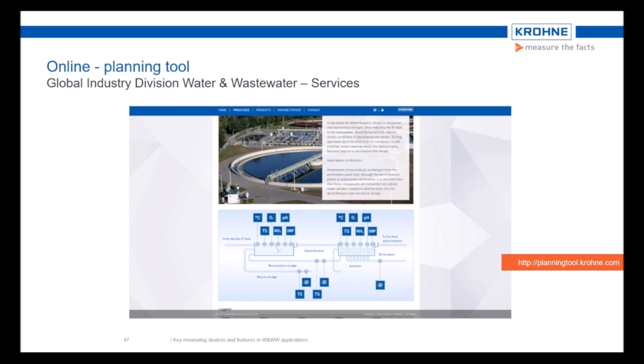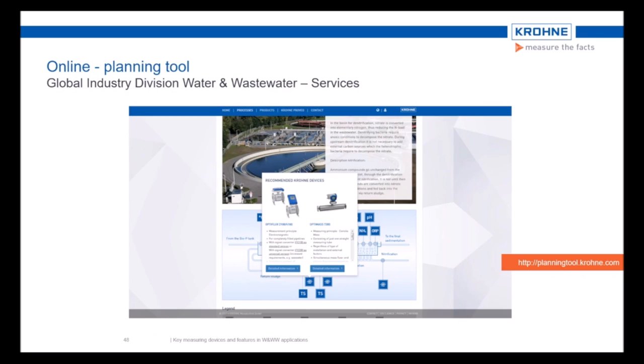Within the graphics, we can see the blue colored icons, which are named and linked to the dedicated measuring devices. For an example, we decide to click the flow button in the return sludge pipe. We then get 2 devices to choose from. In many cases, you get only 1 device, which is available at this point. But in some cases, mostly flow or level, you get more alternatives for your measuring points, like in this case, where we get 2 devices. However, we only recommend the most suitable device types at this point, with of course additional information to get the right choice.